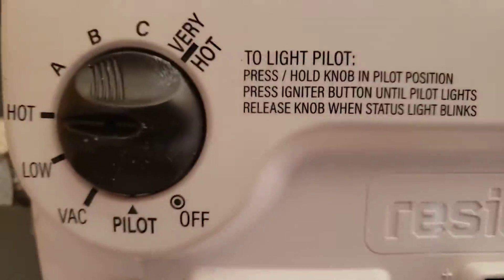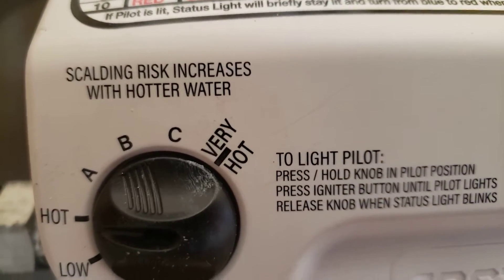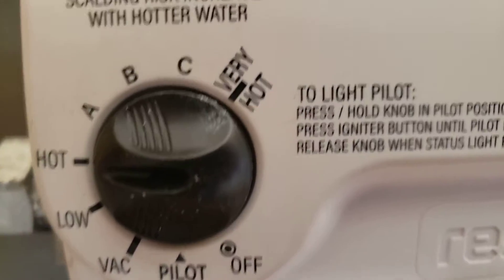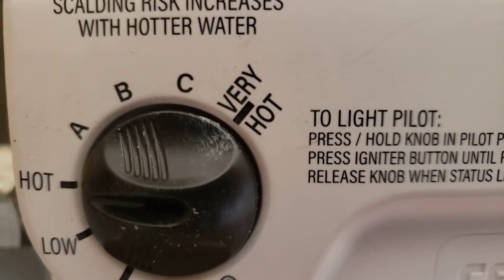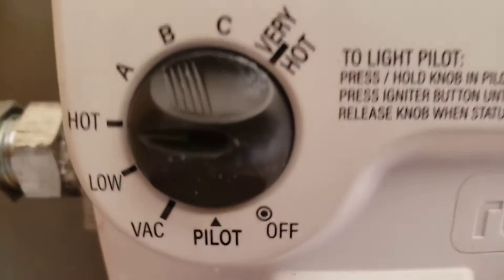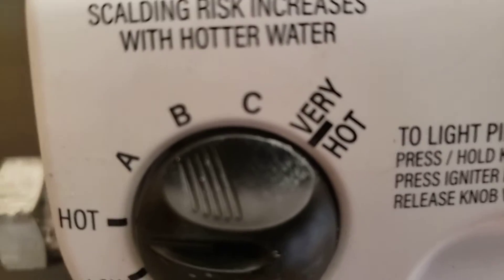Right now the water is set to approximately 120 degrees. You can see the notice here: scalding risk increases with hotter water. Hot is approximately 120 degrees; A is 130, B is 140, C is 150, very hot is 160. At 140 degrees, you get third-degree burns in three seconds and you're going to the hospital. Infants and elderly with thin skin can be burned at 140 degrees in one second.